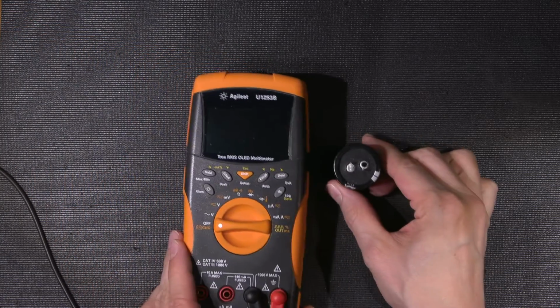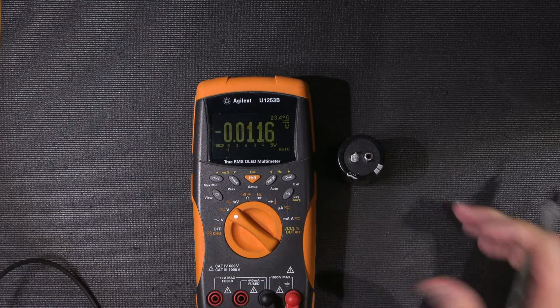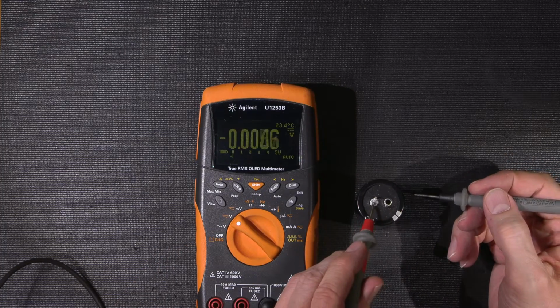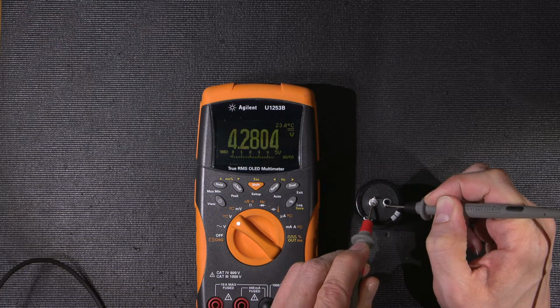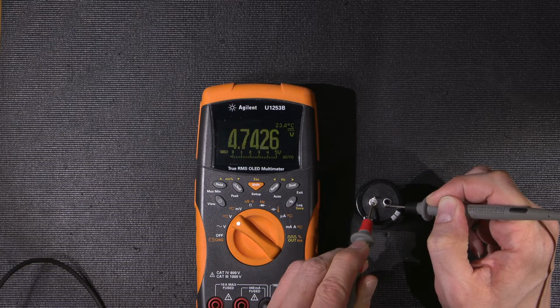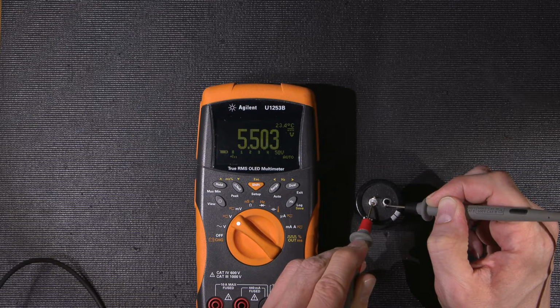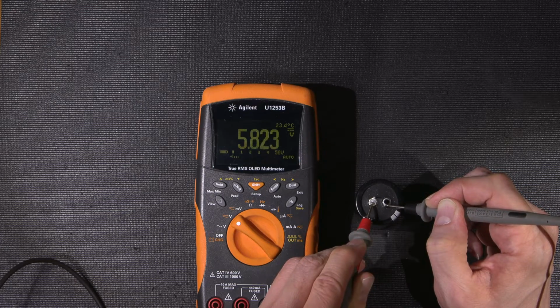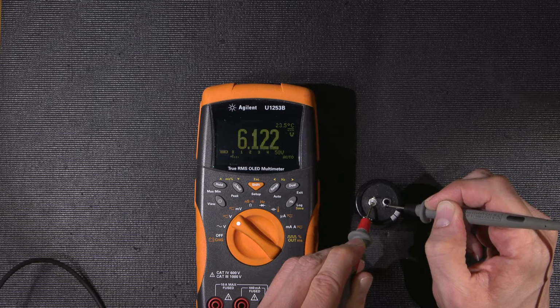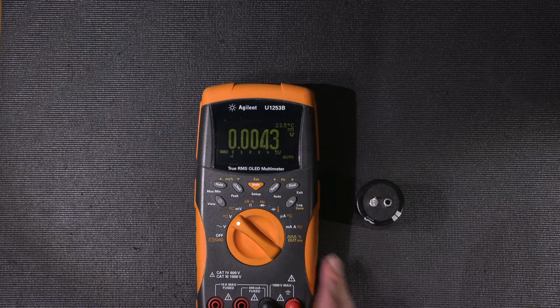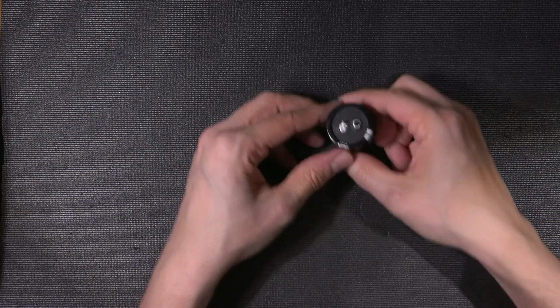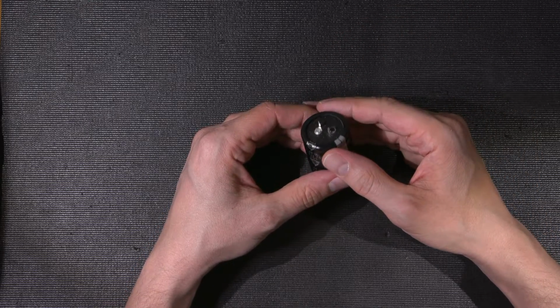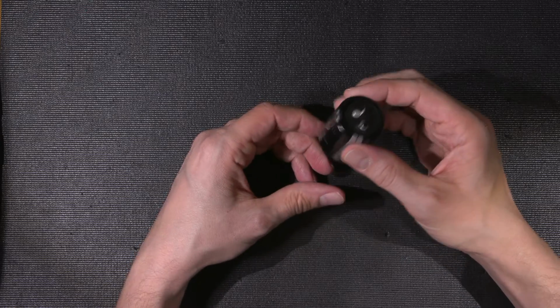Now for something that might be completely unexpected. Dielectric absorption. Let's see what's happening. Look at that. Charging back up. As you can see, this could reach a scary amount of charge in a very short period of time. That's climbing up fast. So, as you can see, this is why a lot of techs, after they discharge these things, put a shorting bar across them. But again, you can't forget, because if you do and you plug the thing in or turn the power back on, you're going to damage the power supply or just destroy it, right? So, something to keep in mind, dielectric absorption is not your friend, in this case, at any rate.